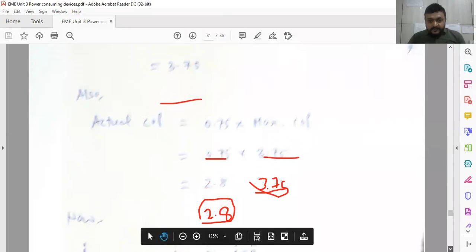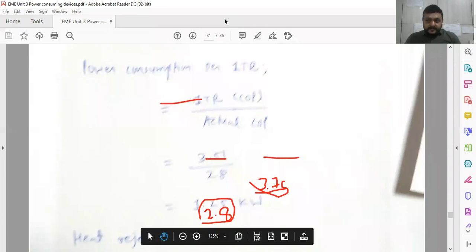So once we have calculated the actual COP, now our main objective is to find out the power consumption and heat rejected. So power consumption per ton is equal to 1 TR divided by actual COP. Now 1 TR is equal to what? We already derived the standard 1 TR, that is 3.51 or 3.88, but we are ideally taking it as 3.51, as we derived in the initial section, divided by the actual COP, that is calculated 2.8. So your answer is 1.25 kilowatts. So that 1.25 kilowatt is the power consumption in this system.